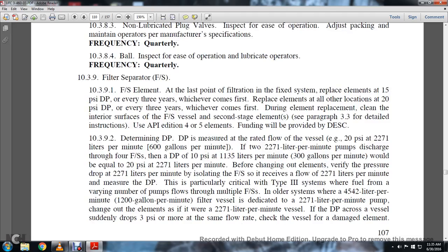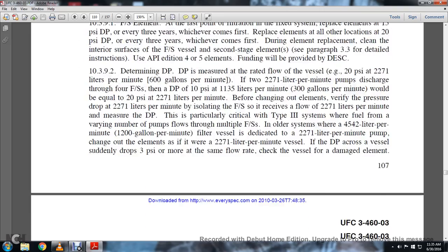If the DP across the vessel suddenly drops 3 psi or more at the same flow, check the vessel for a damaged element.